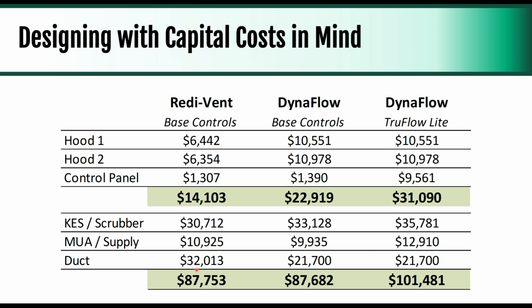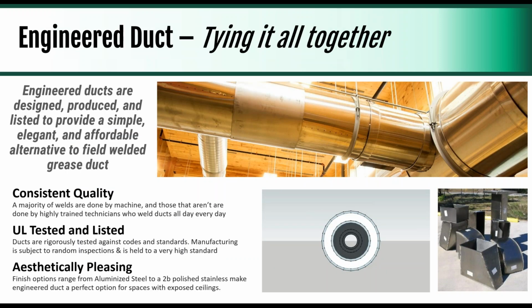But here where we saw a really big difference was actually the ductwork. Because you were reducing that duct run size from 24 inches to 20 inches, I think was the difference, you're actually saving significantly on the engineered duct run. So you can have high efficiency hoods for no real increase in capital costs. To go to the demand control, yep, you've got a slight increase in capital costs, but when we look at what that means from an energy savings perspective, you'll see that that payback is actually pretty quick.